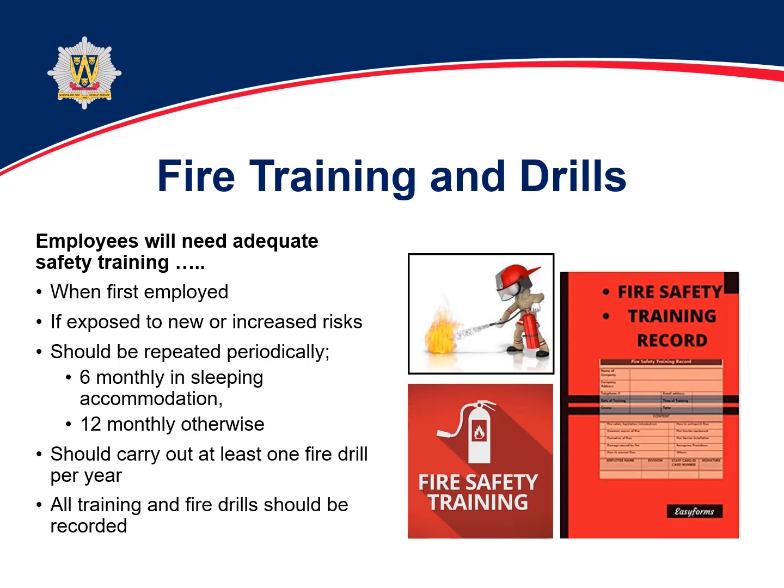Fire safety training and drills. So as we said, this is based on your emergency action plan and would be carried out at regular intervals. So for example, when you're first employed, when you have an increase in risk, changes in working practices. It should be repeated periodically. We recommend 6 monthly for sleeping accommodation and 12 monthly in all other places.